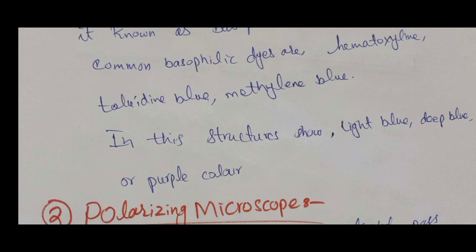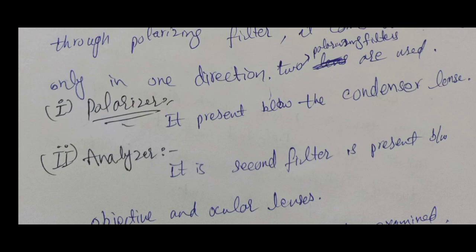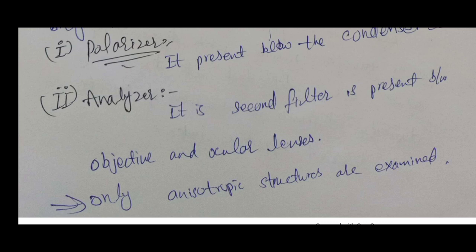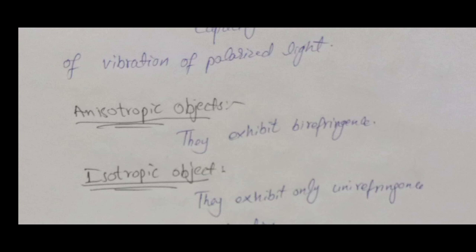The second type of light microscope is the polarizing microscope. In this microscope, the light comes out vibrating in one direction. There are two polarizing filters: the polarizer, located below the condenser lens, and the analyzer, located between the objective lens and the ocular lens. Only anisotropic structures can be examined by the polarizing microscope. Anisotropic structures show birefringence or double refraction — the capacity to rotate the direction of vibration of polarized light — while isotropic objects show only unirefringence or one-directional refraction.